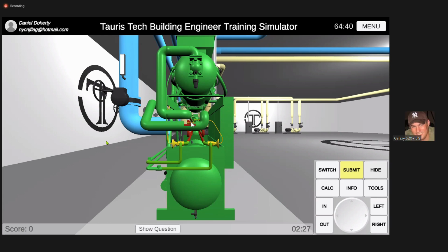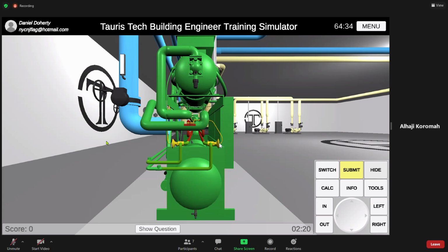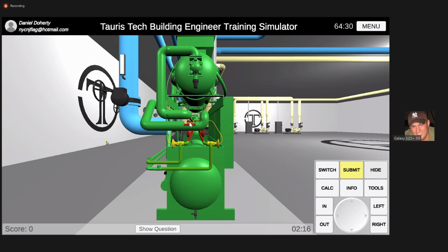So then how does it open up the diaphragm? What has to happen to... give it back to you. Oh, I'm sorry guys, that's right. So you have liquid refrigerant in this bulb, right? It senses a superheat, the refrigerant boils off and applies pressure from the expansion downward on the diaphragm. And that's how the TXV operates.